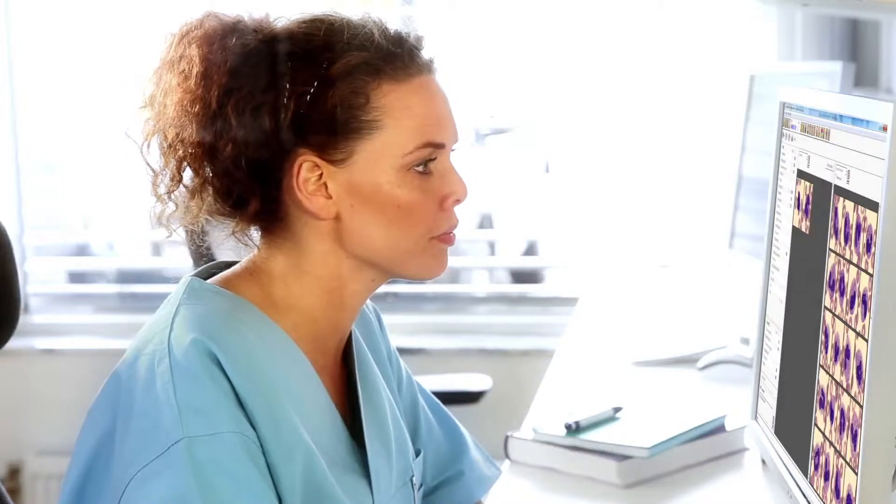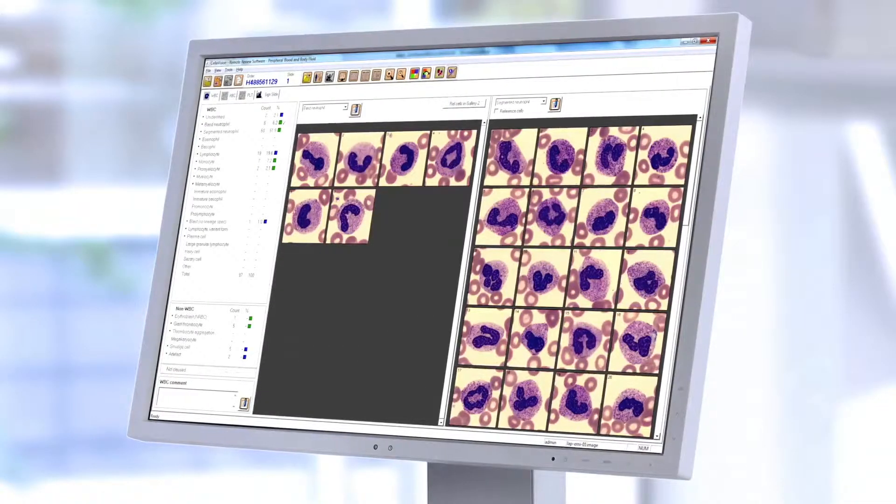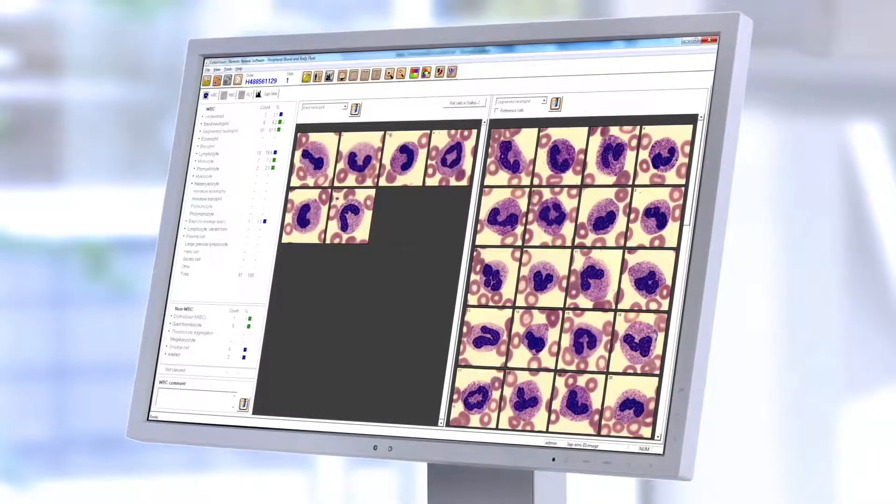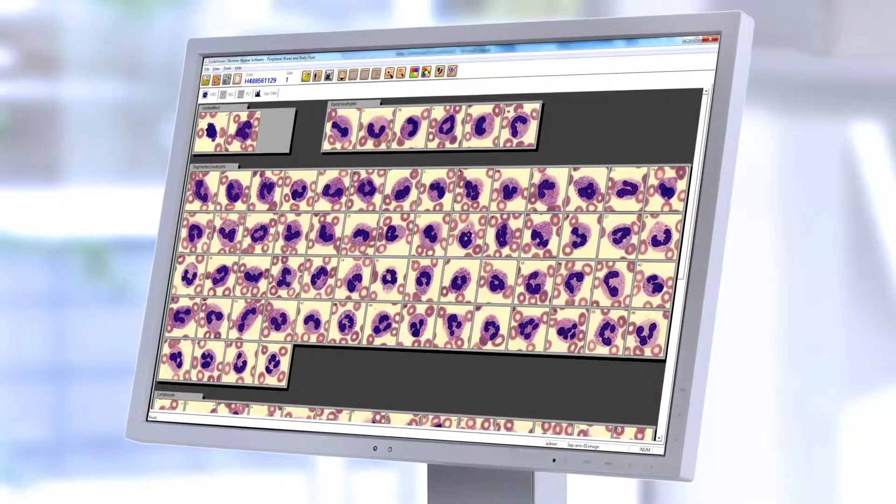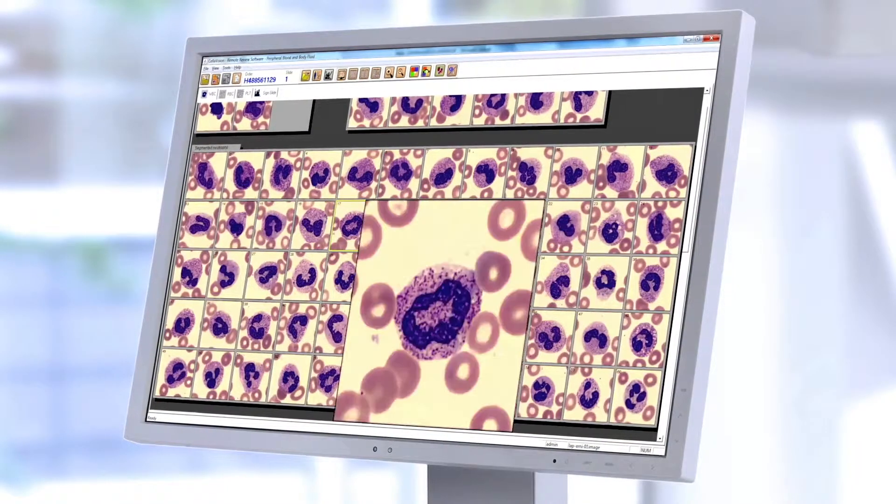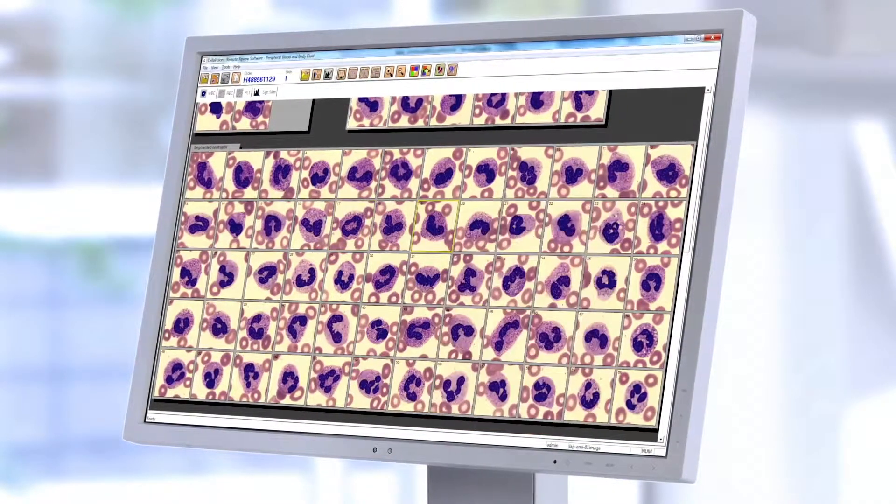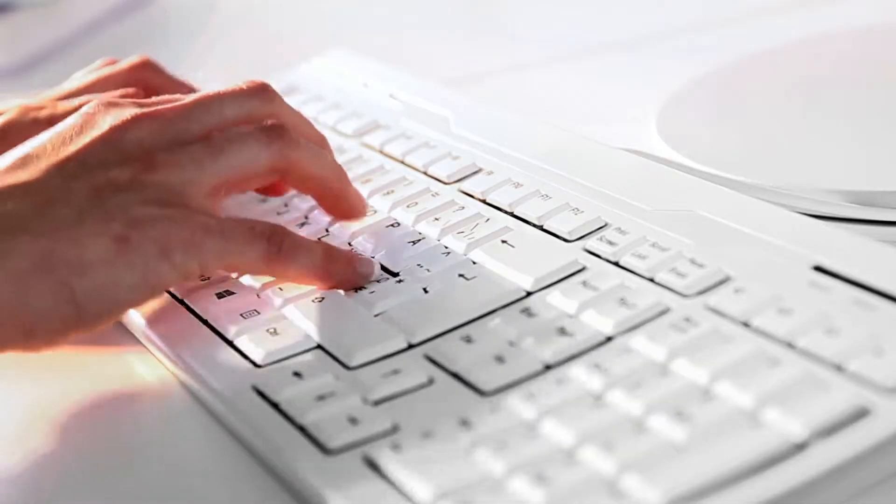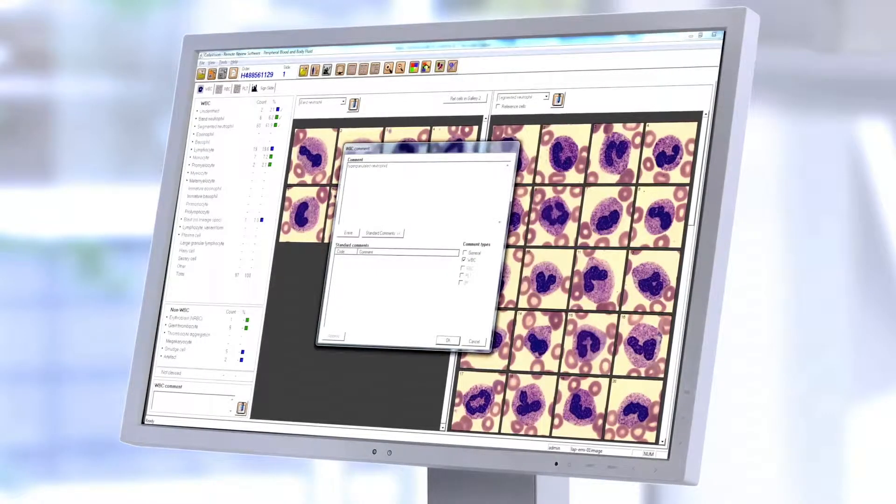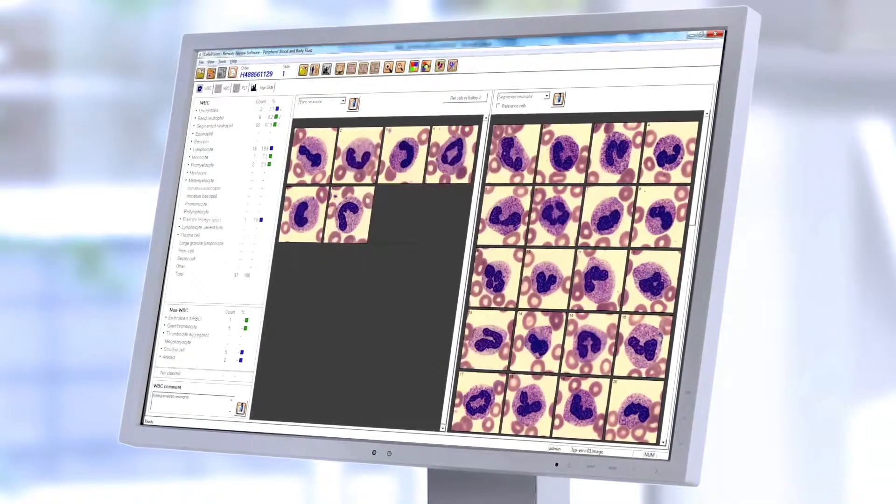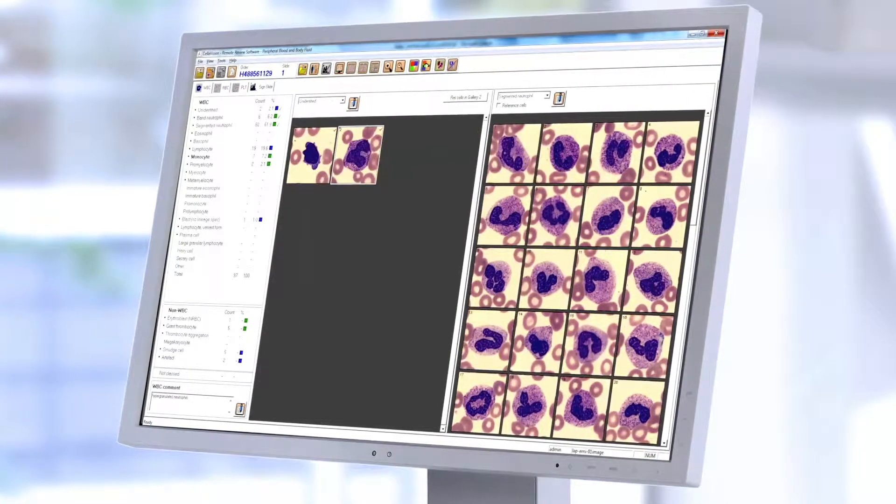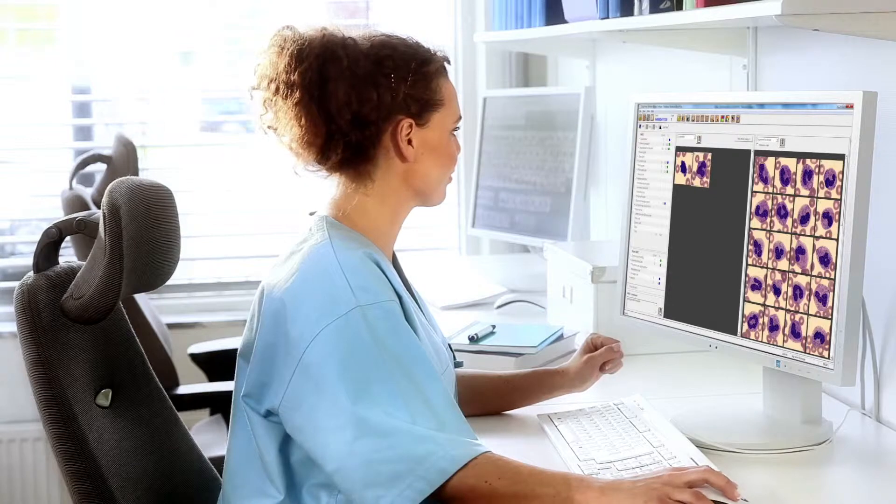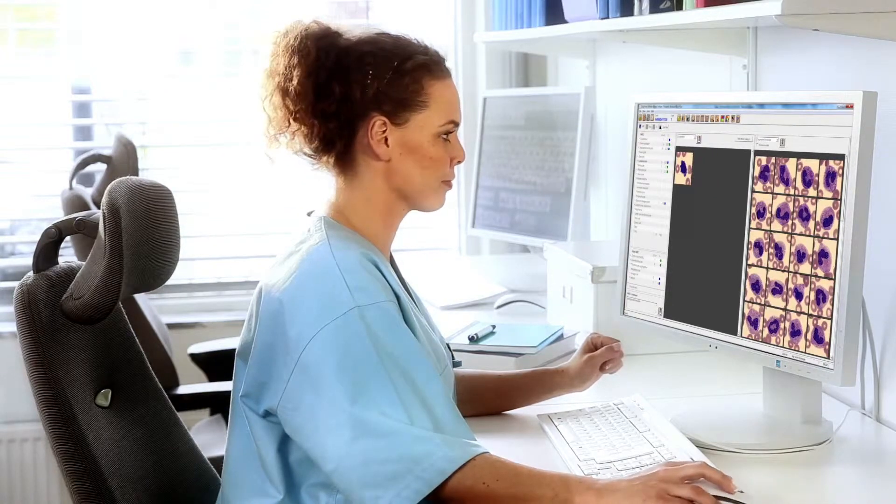The addition of a digital cell morphology instrument has greatly changed the way we evaluate peripheral smears. Some technical challenges remain, including evaluation for rare cells and certain microorganisms. All systems require careful evaluation and validation. Parallel manual review is recommended for certain case types as laboratories become more proficient with these systems.